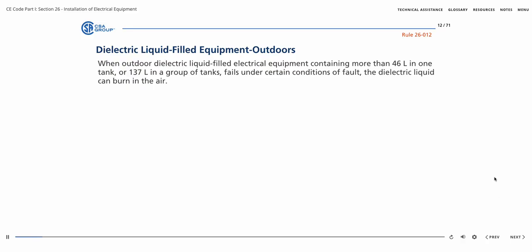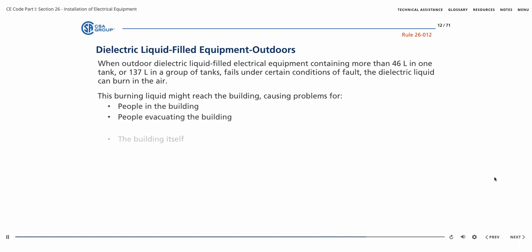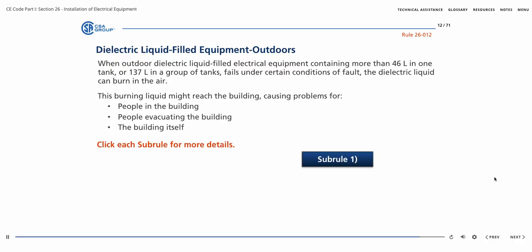When outdoor dielectric liquid-filled electrical equipment containing more than 46 liters in any one tank, or a total of 137 liters in a group of tanks, fails under certain conditions of fault, the dielectric liquid can burn in the air. This burning liquid, as well as any leaking dielectric liquid, might reach the building, causing problems for people in the building, people evacuating the building, and the building itself.